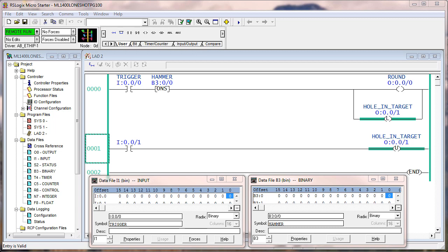You can interpret the bit memory as on off based on whether or not it was a true if on, true if off instruction. But the highlights on the instructions to the left do not indicate on off. They indicate true false. Do the graphical highlights of the instructions to the right indicate true false? No, they don't. They indicate on off.